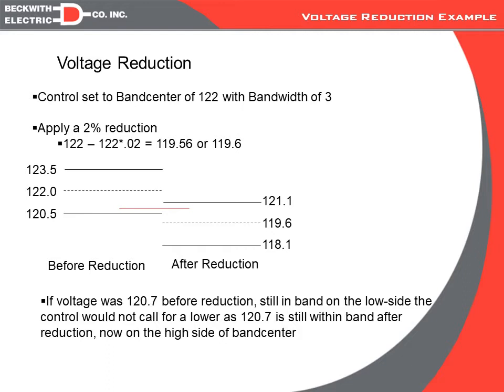Now, when we request a 2% reduction, all we're doing is telling the control to use a new band center. So it's going to take the existing band center of 122 with a bandwidth of 3, and it's going to multiply and reduce that band center by 2%, which would then change it to 119.6. And at 119.6, we're still going to have the same 3-volt bandwidth.